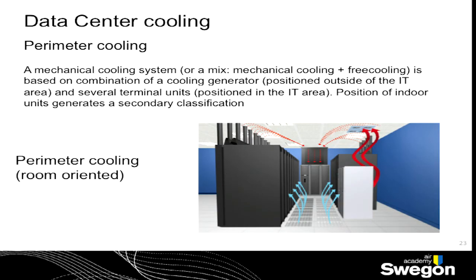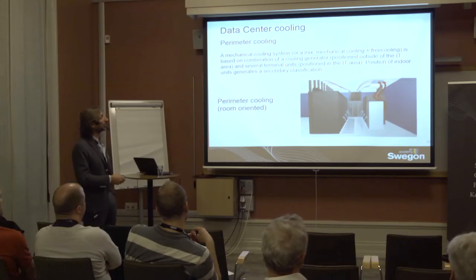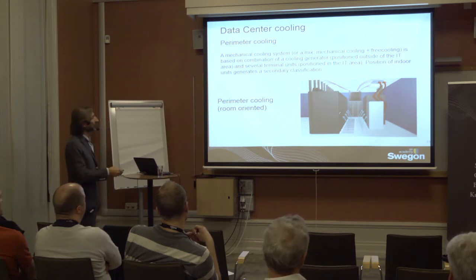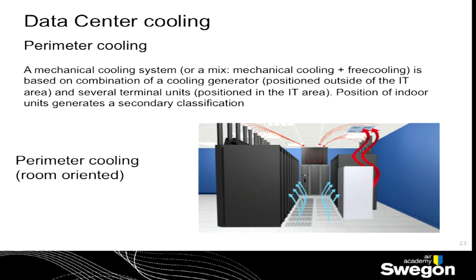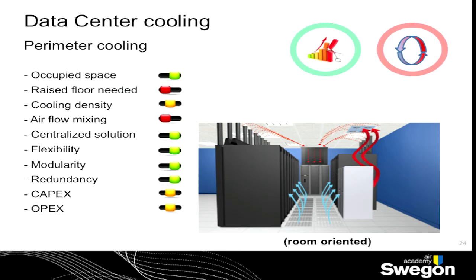Another classification can be made considering the location of the CRAC units inside the building. And it is very important to consider it because it can affect the efficiency of the system. In a perimeter cooling system, where the CRAC units are just on the perimeter of the room, we have a room-oriented system, which has its pros and cons. I think the main con that we have to consider is the airflow. As we investigated before with Morgan, a system like this one, if it is not upgraded with containment, can have a very high rate of recirculation, decreasing the efficiency of the system.